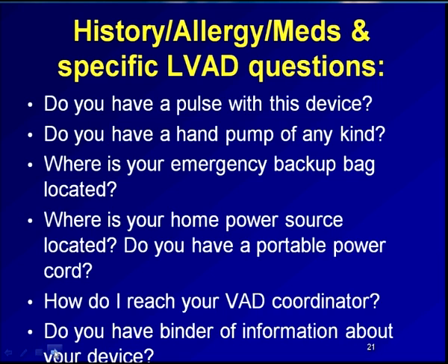Where is your emergency backup bag located? If you're in the home, find out where that bag is located. If they're in their car from an auto accident or you're picking them up at a shopping center, find out where in the car that bag may be located. Some of these patients may not take that emergency bag with them because they think they're just going to be gone for 10 minutes. But it's an important question to ask. And this backup bag should have extra batteries, an extra controller. Any emergency intervention tools that they need for the device should be in that backup bag.